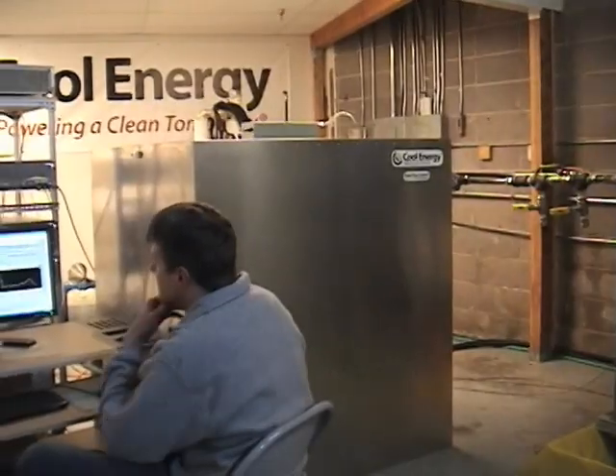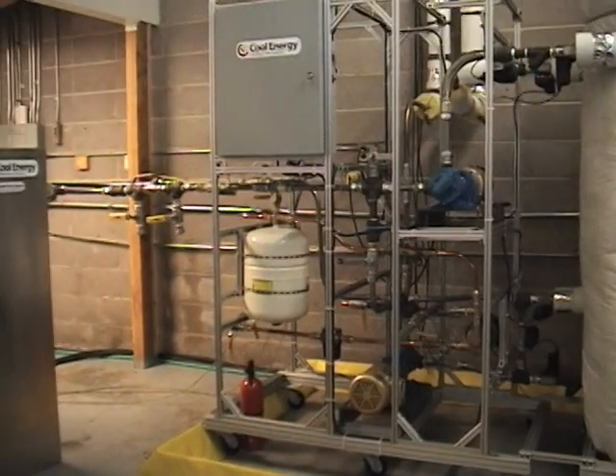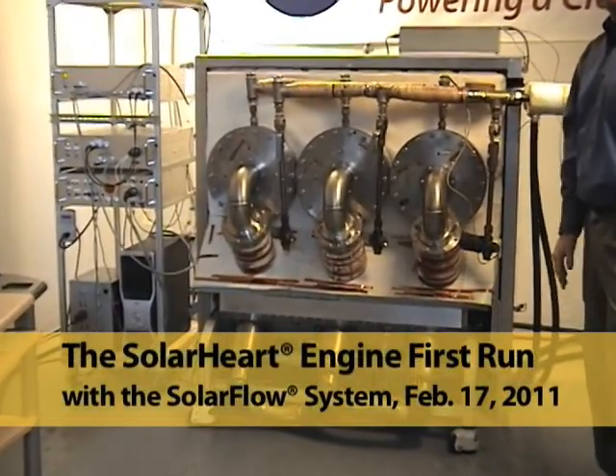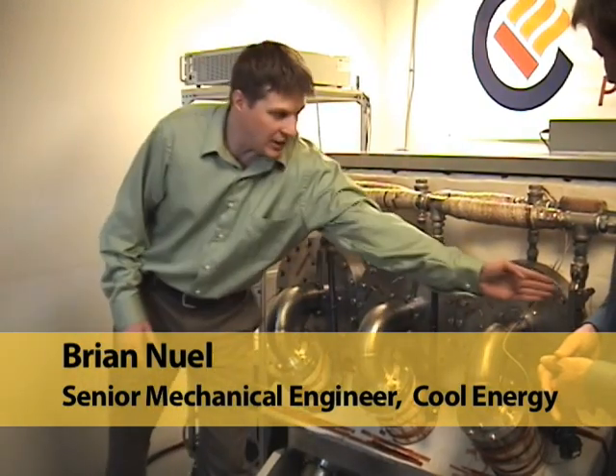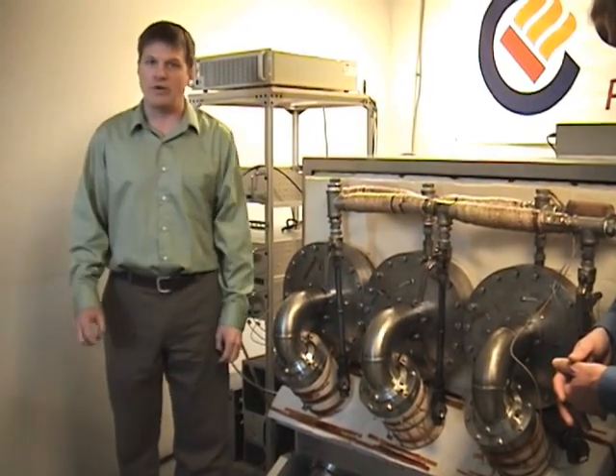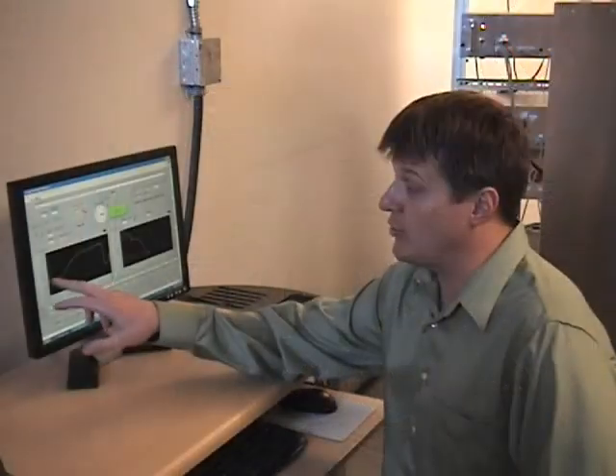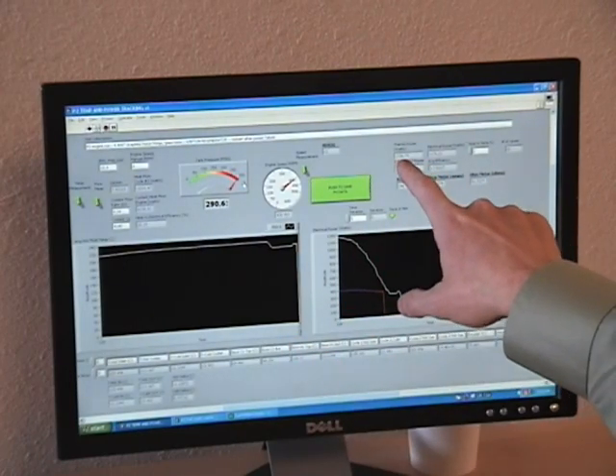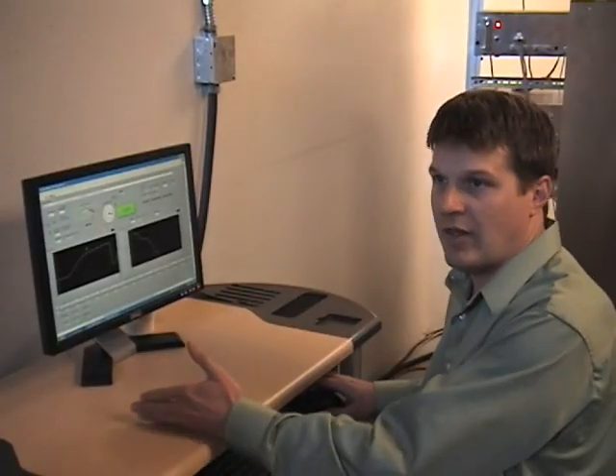In our pilot solar flow system, you can see its main components: the solar thermal collectors, the thermal storage tank, the pump station, and the SolarHeart engine. This solar flow system produces over 1,500 watts of power. We have sensors scattered throughout the engine monitoring various temperatures, pressures, and fluid flow, all linked back to the computer and recorded in the lab. We monitor input temperatures on both the hot and cold sides, engine speed, electrical power output, and flow rates in both the cold and hot fluid.